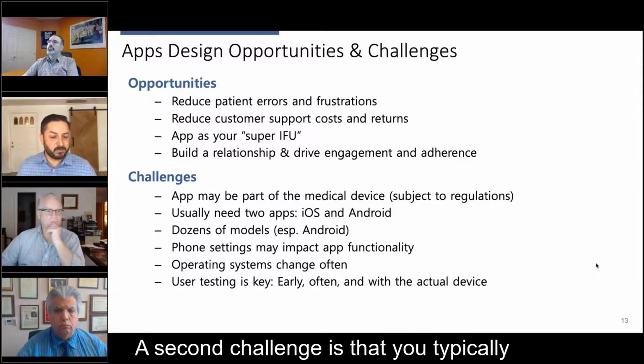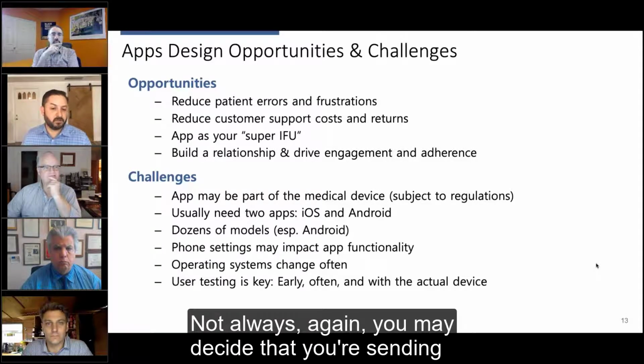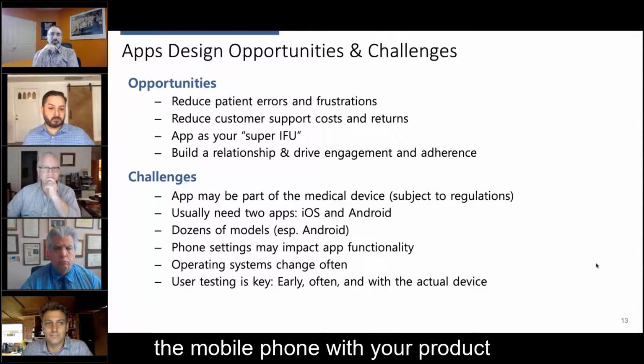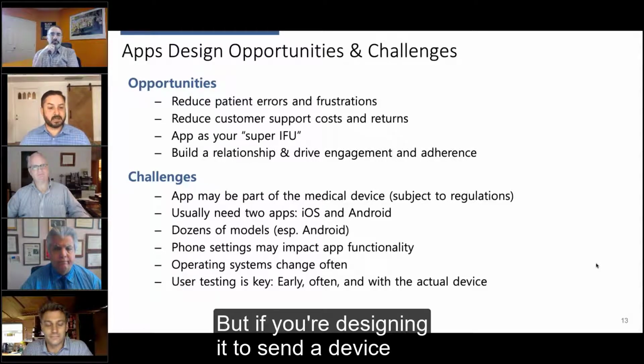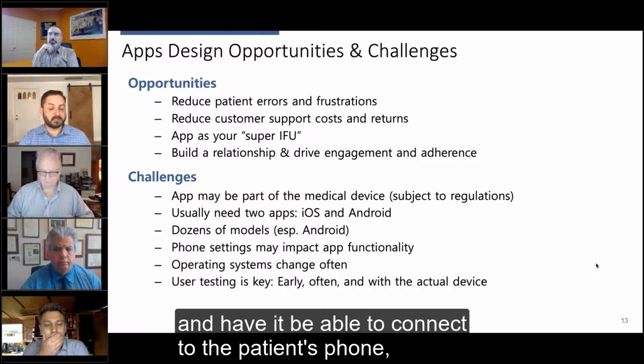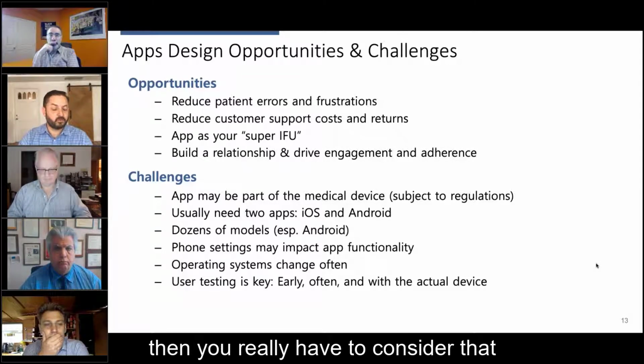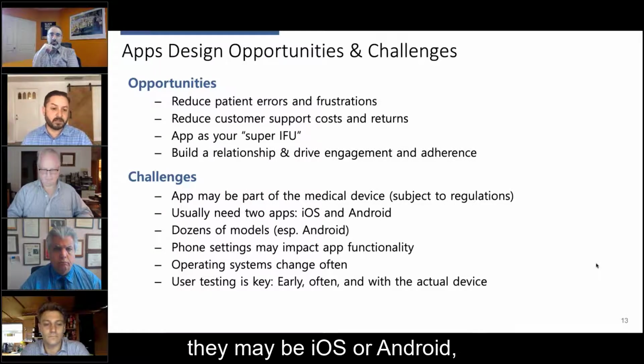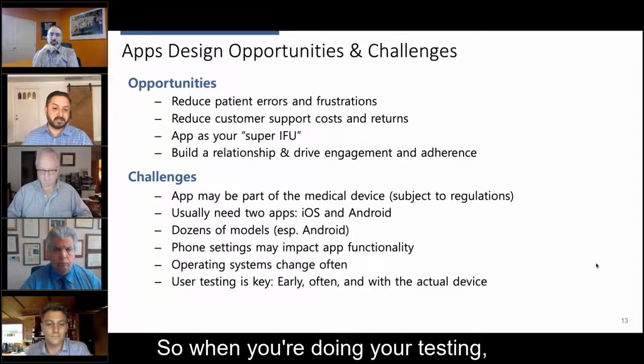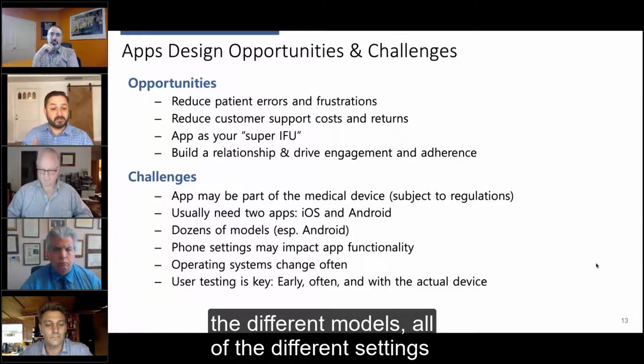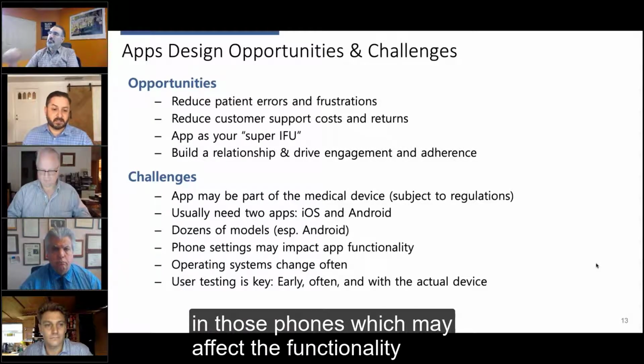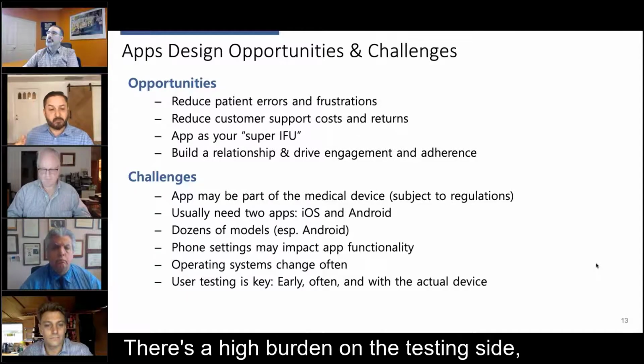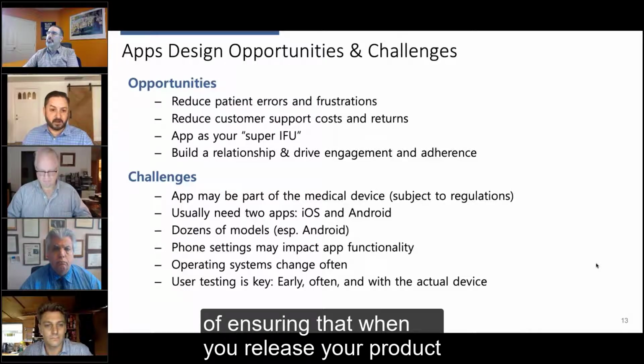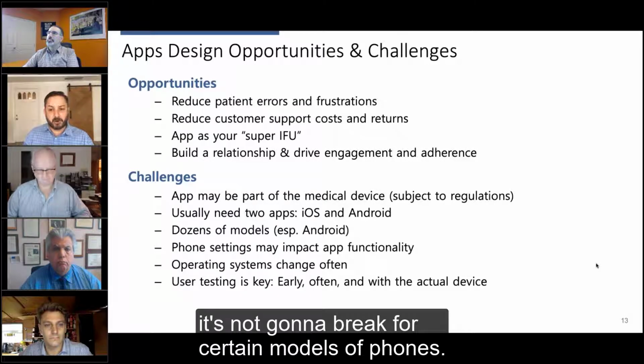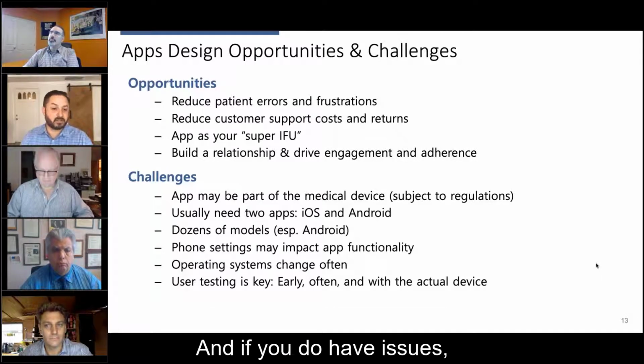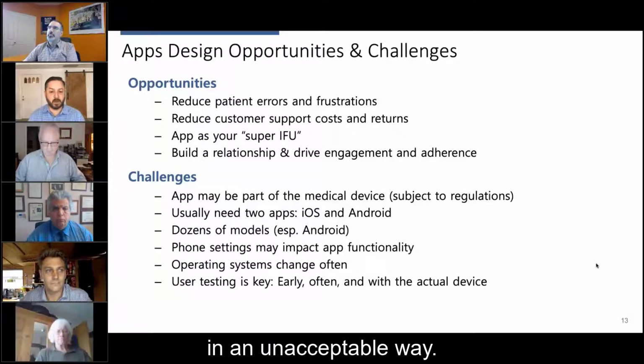A second challenge is that you typically are going to want to develop two apps. Not always. Again, you may decide that you're sending the mobile phone with your product because you don't want to deal with this. But if you're designing it to send the device and have it be able to connect to the patient's phone, then you really have to consider that they may be iOS or Android, and that there could be dozens of models. So when you're doing your testing, you really have to account for all of the different models, all of the different settings in those phones, which may affect the functionality of the device. So there's a high burden on the testing side of ensuring that when you release your product and when you release updates, it's not going to break for certain models of phones. And if you do have issues, that they're not going to impact patient safety in an unacceptable way.